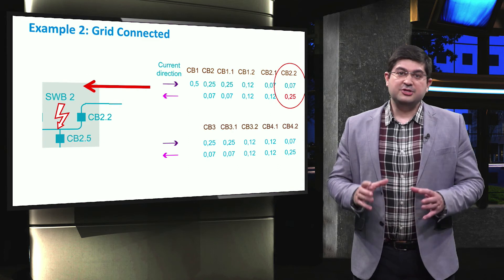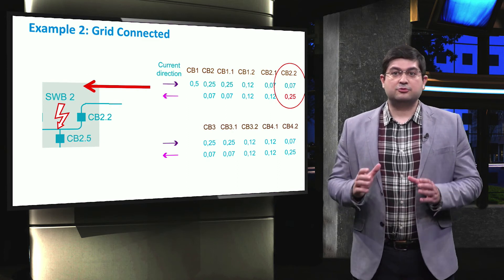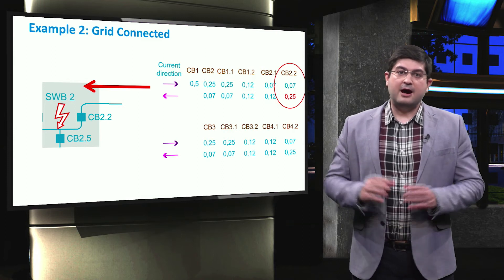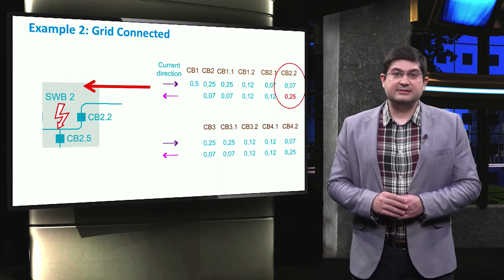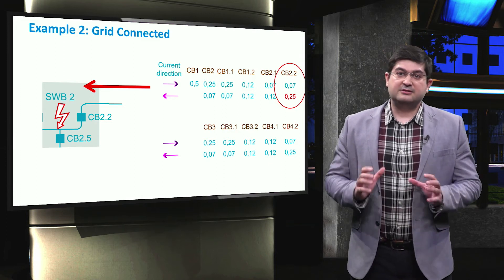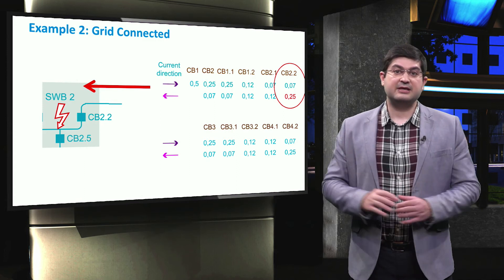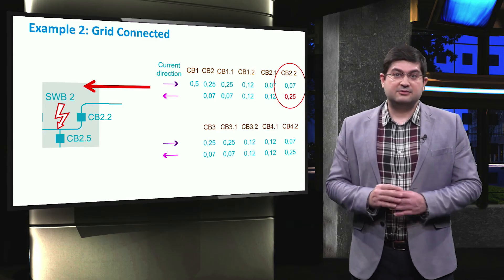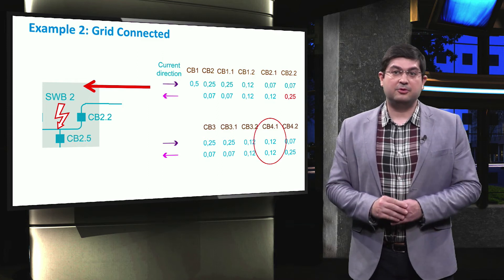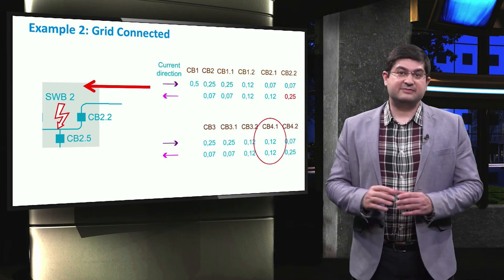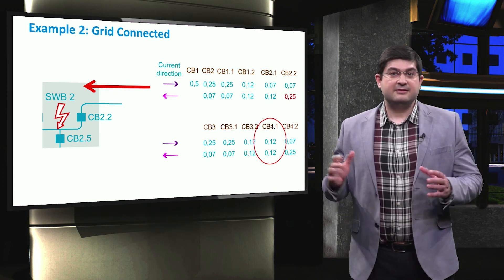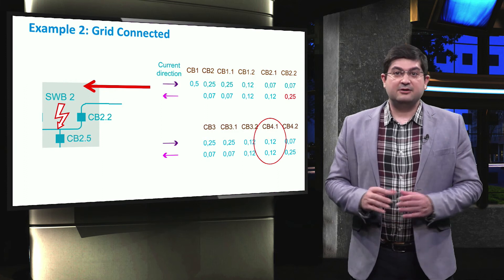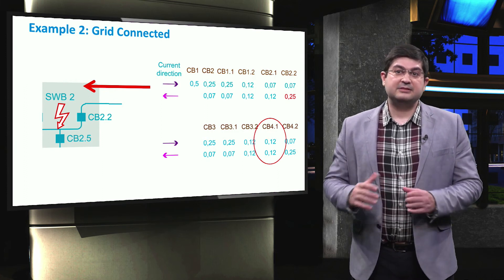During the first fault, the configuration of the grid was changed such that switchboard 2 was connected to switchboard 4. However, the typical time setting of the relays was designed for the first example, where the time setting of switchboard 2 for the fault current from right to left is 0.25 seconds. This value is relatively large, as circuit breaker 2.2 should disconnect faster. If circuit breaker 4.2 does not trip, then circuit breaker 4.1 will trip within 0.12 seconds, which is faster than circuit breaker 2.2. As a result, switchboard 4 is inappropriately disconnected from the grid.